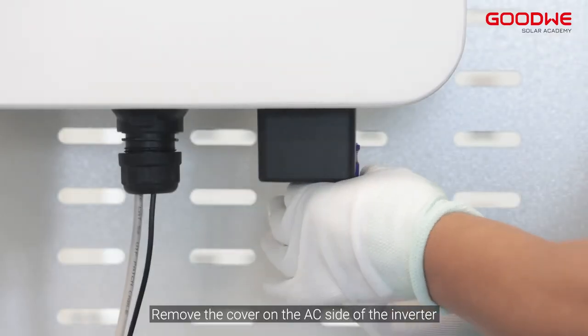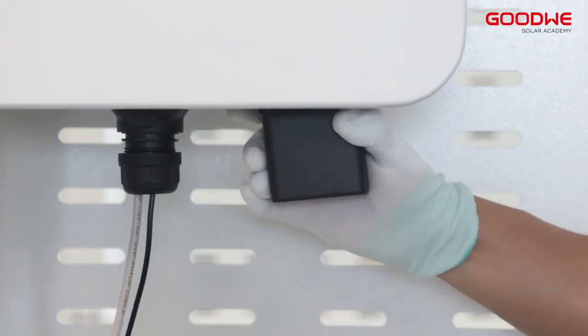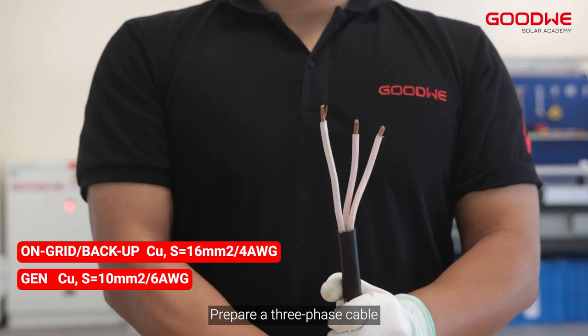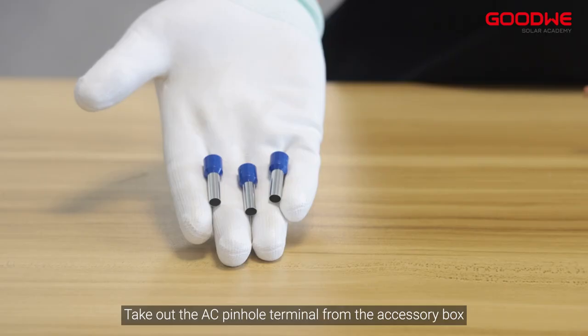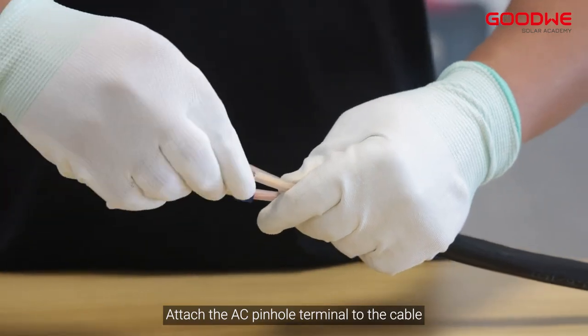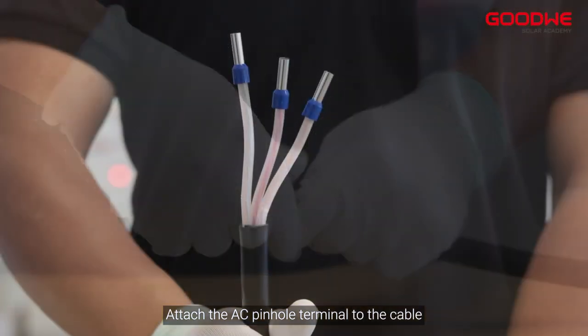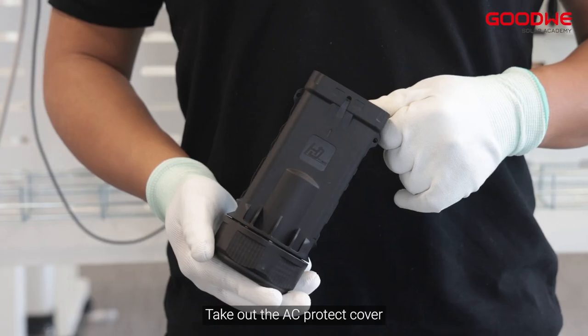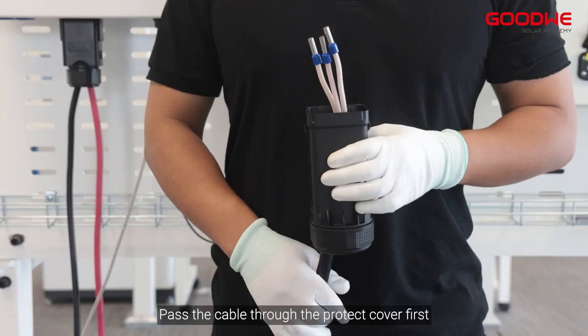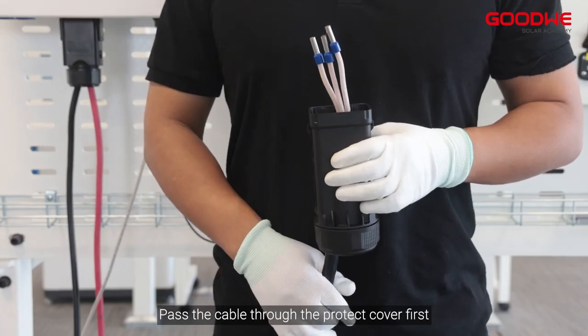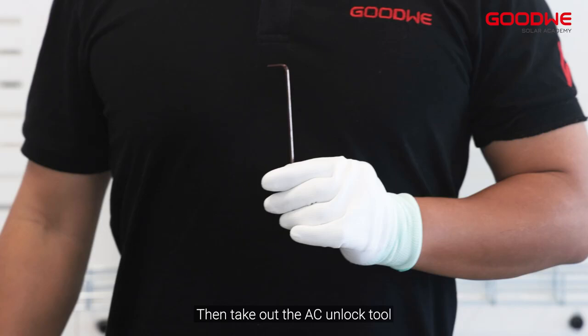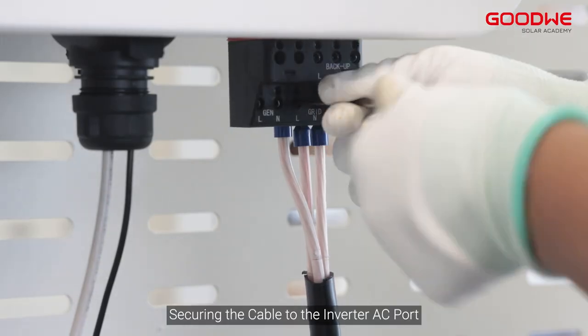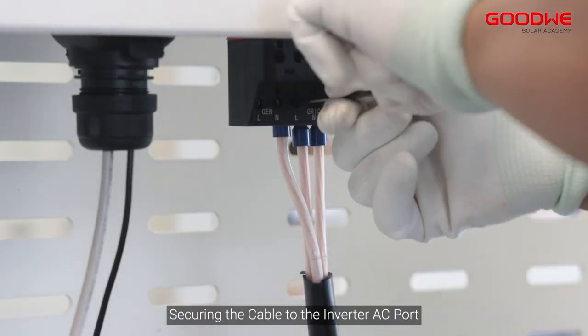Remove the cover on the AC side of the inverter. Prepare a 3-phase cable. Take out the AC pinhole terminal from the accessory box. Attach the AC pinhole terminal to the cable. Take out the AC protect cover. Pass the cable through the protect cover first. Then take out the AC unlock tool, securing the cable to the inverter AC port.